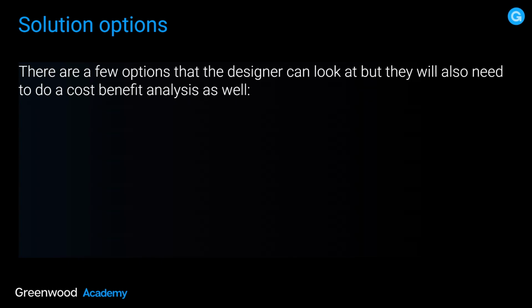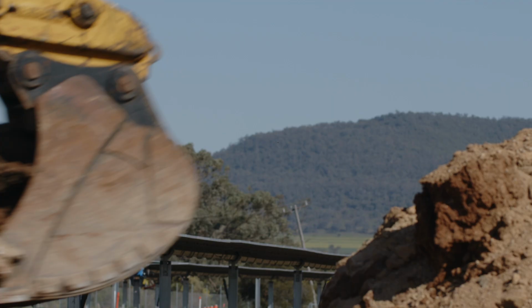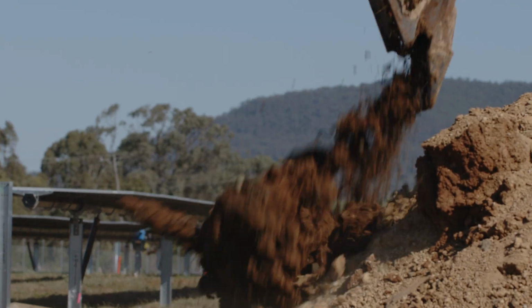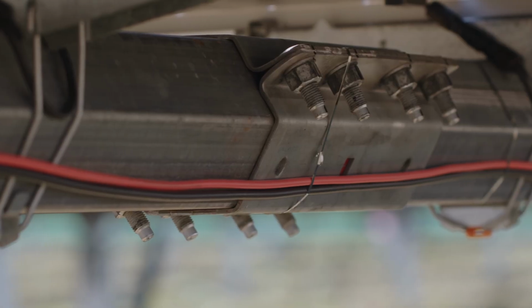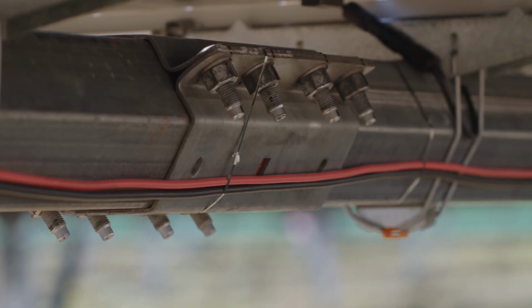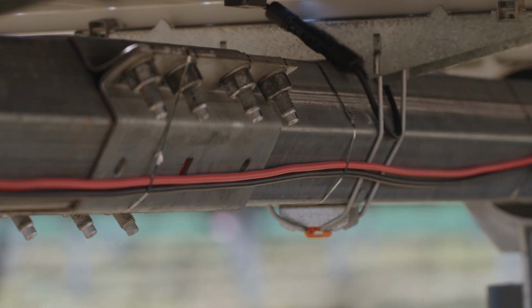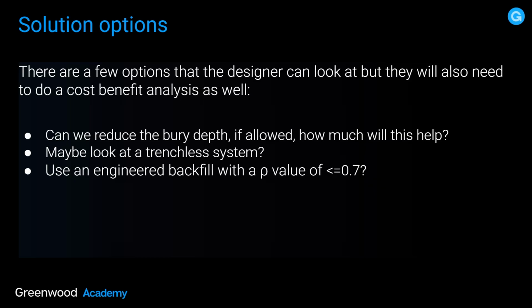Solution options. Now there are a few options that the designer can look at, but they will also need to do a cost-benefit analysis as well. Can we reduce the bury depth? If allowed, how much will this help? Maybe we're going to look at a trenchless system, or use an engineered backfill with a thermal resistivity value of less than or equal to 0.7. So this is the question that the designer has to work out well before anything starts on site.